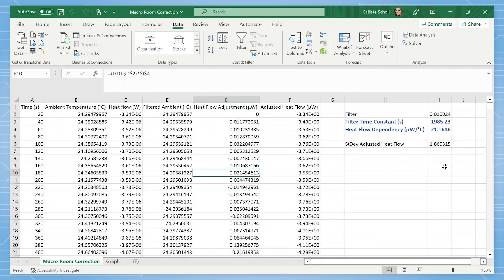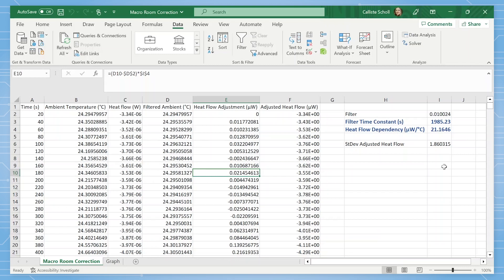You should also notice the filtered ambient, heat flow adjustment, and adjusted heat flow columns have been updated. It is the filter time constant and heat flow dependency values you will want to take note of because we will put these values into TAM Assistant to correct for the large ambient temperature changes in the device settings.